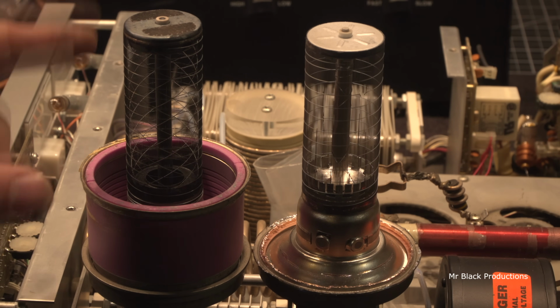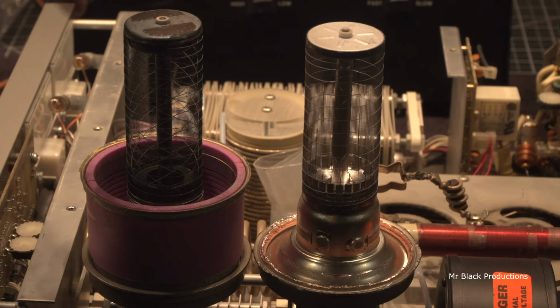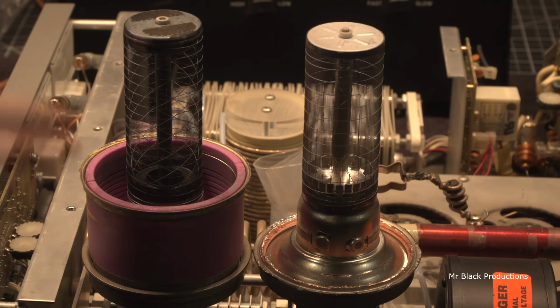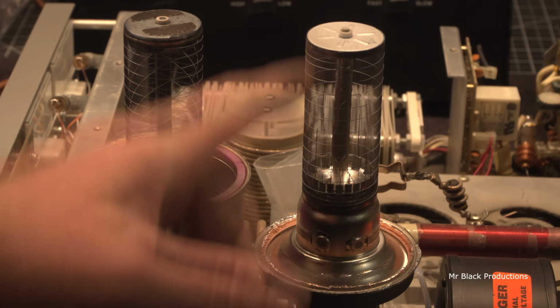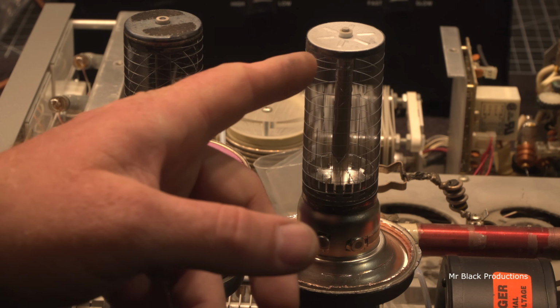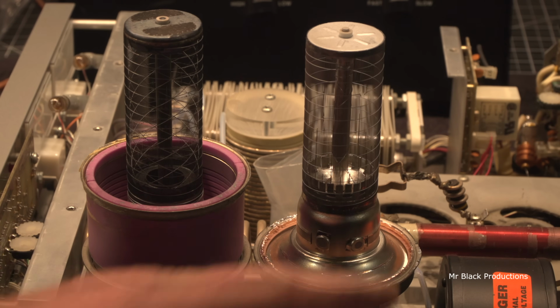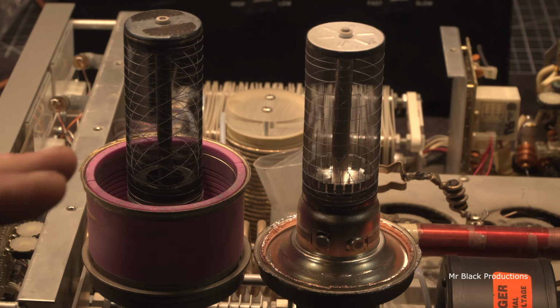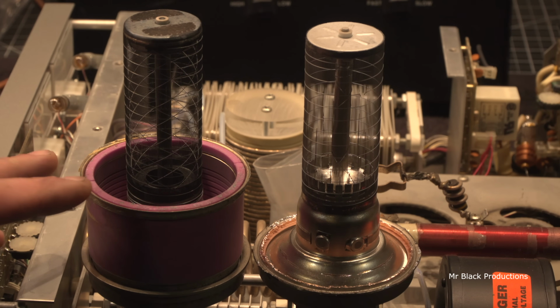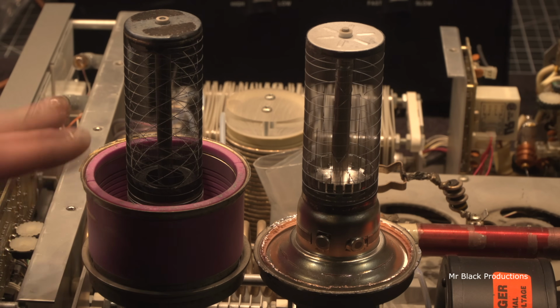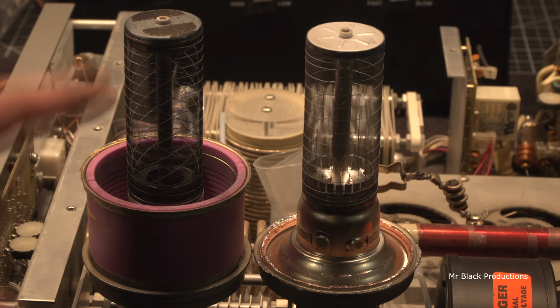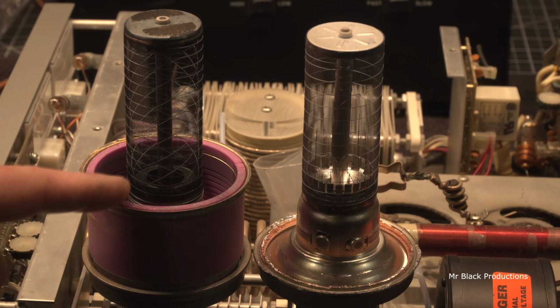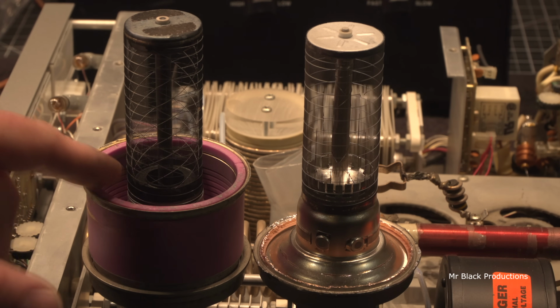The outside is a vertical screen and then held together with a spiral wrap backer, where this is a vertical outside screen and a horizontal wrap. That's what differentiates the two. They achieve the exact same job. They're just slightly different. This one here has lost its vacuum at some point in its life. And it was a slow leak because this thing was obviously in operation and the filament was lit. Look at how dark the inside of this is.